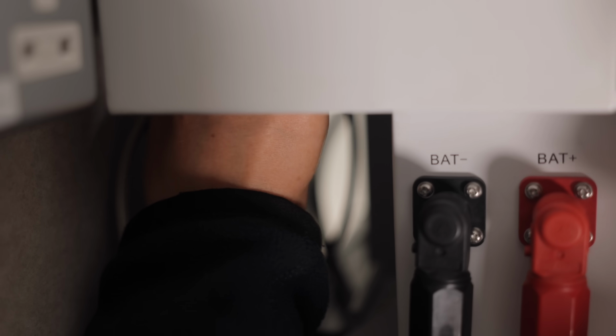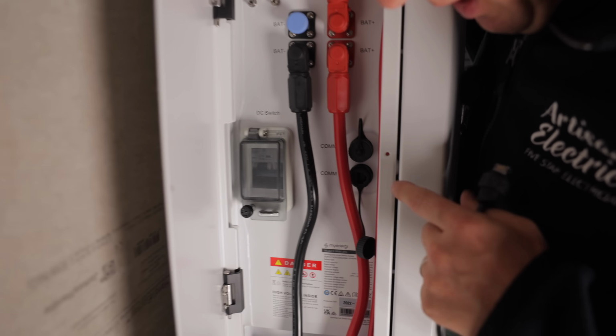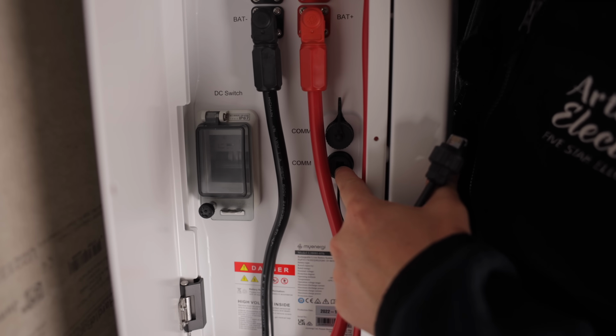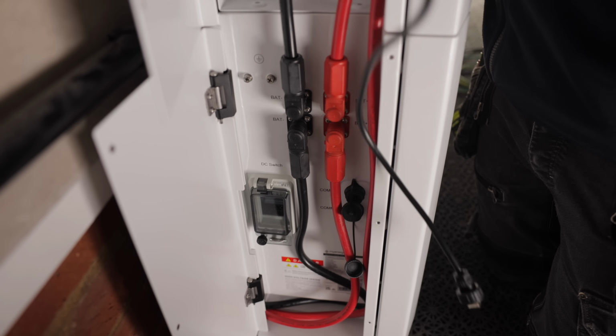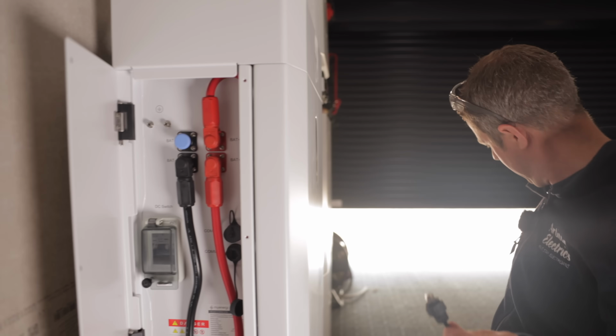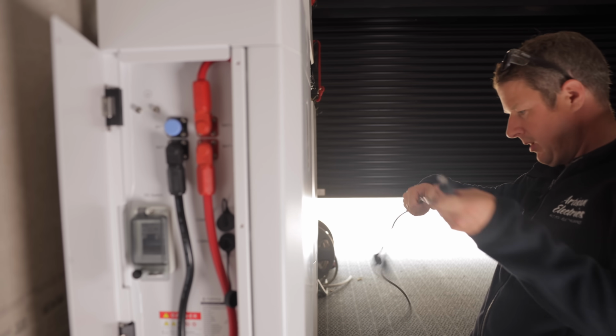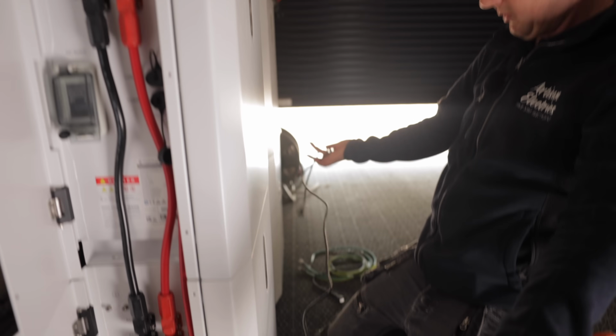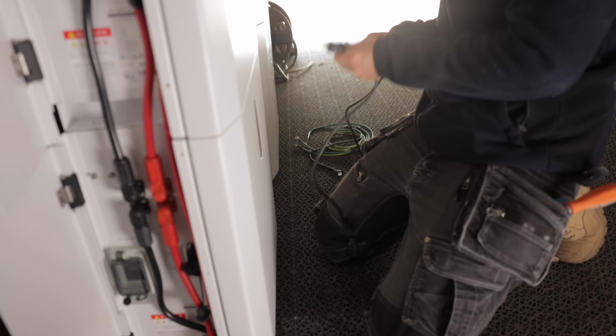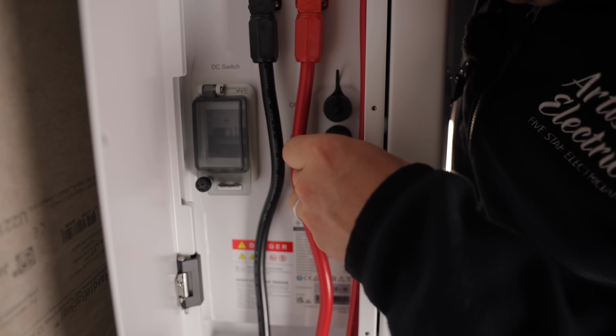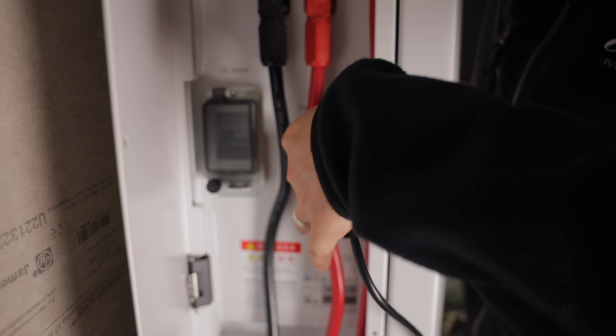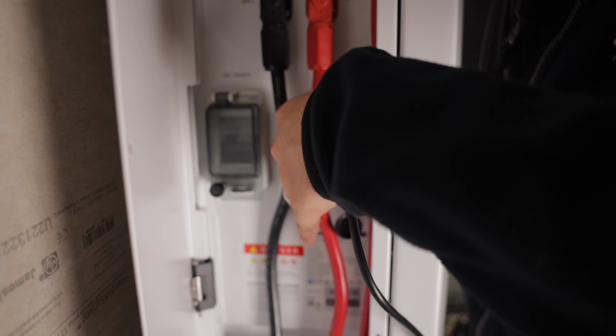Then you've got all these comms cables that go between the battery modules - they just go from the bottom socket to the top socket, bottom socket to top socket, etc. There must be a long one that goes between the two bottom modules, that's part of the long cable kit, and that just plugs in there. Then again you screw the gland on so it holds it in place - you don't want it pulling out and losing communication between the batteries.